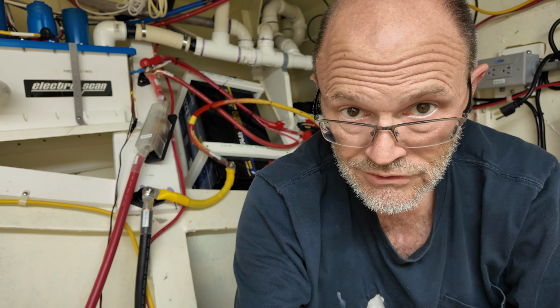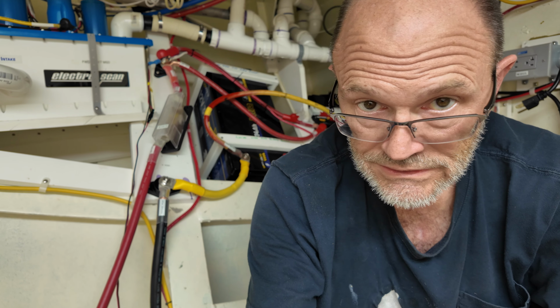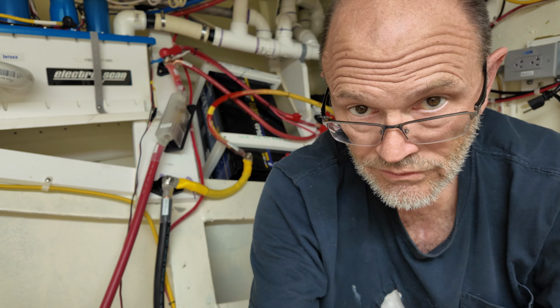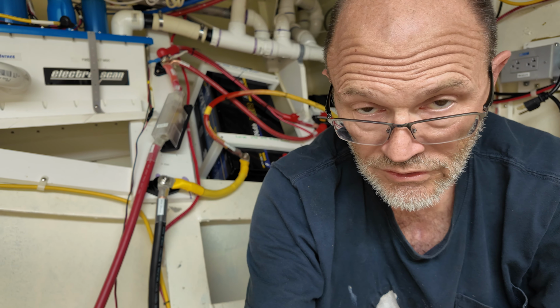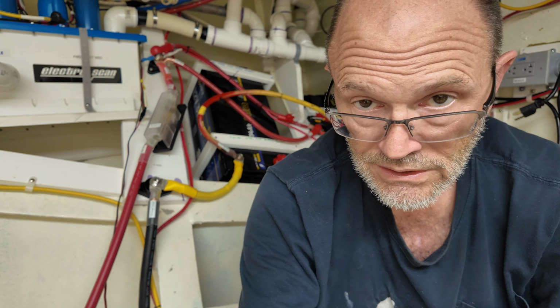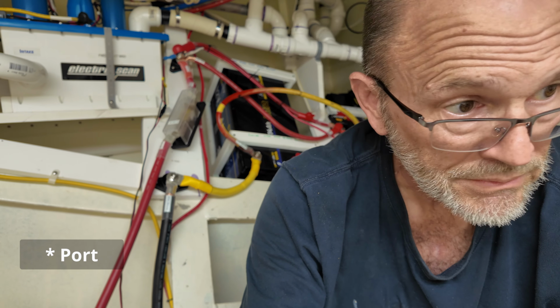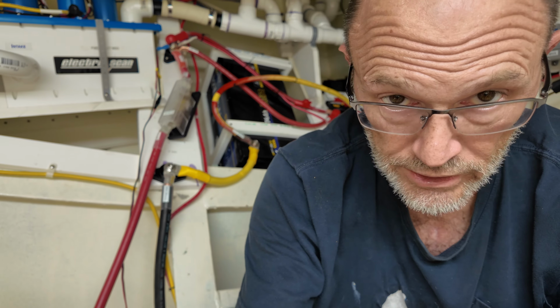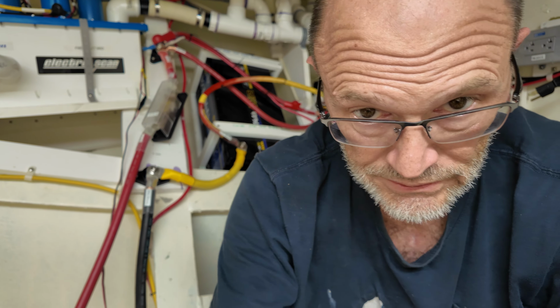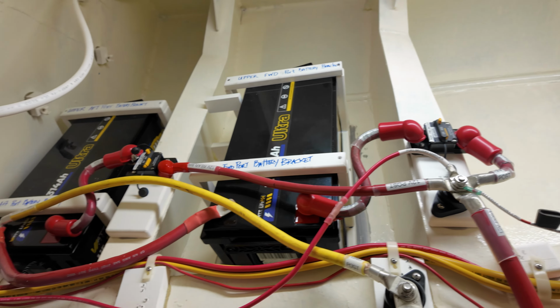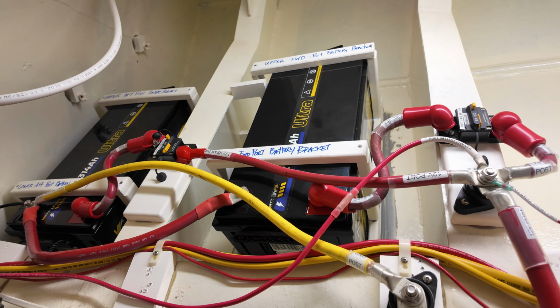To summarize, where are we at? We are able to make the bow thruster run for 1 or 2 seconds in either direction. So the dirty solenoid was definitely the issue with going to starboard. But now we need to do current measurements on the bow thruster, confirm what it's pulling, and then also do it on the individual battery banks, then on the individual batteries.